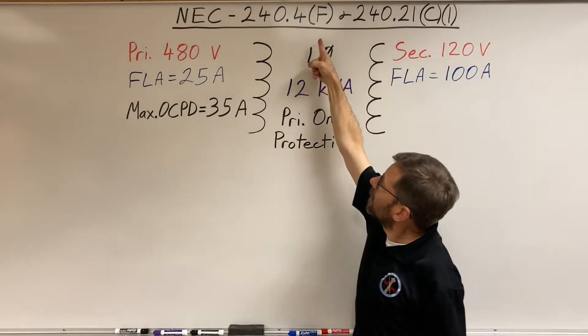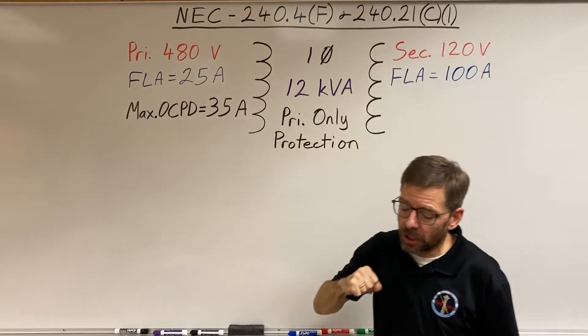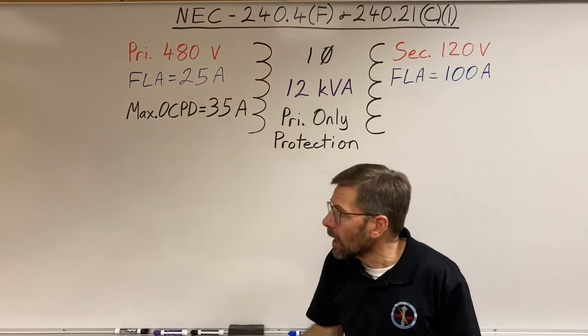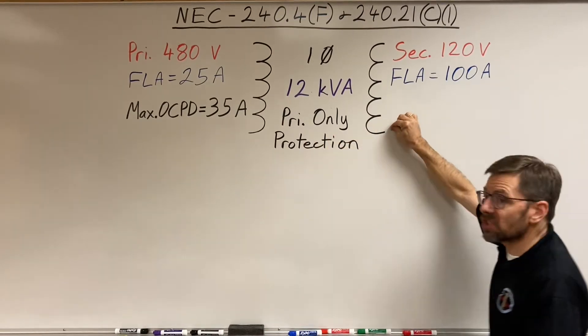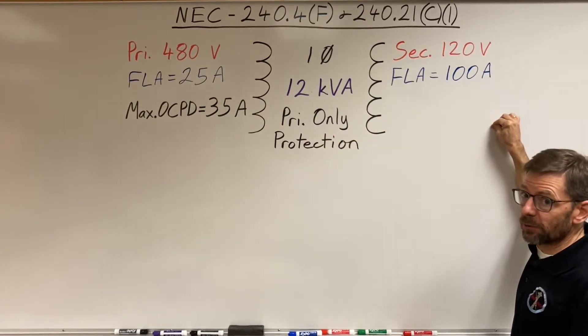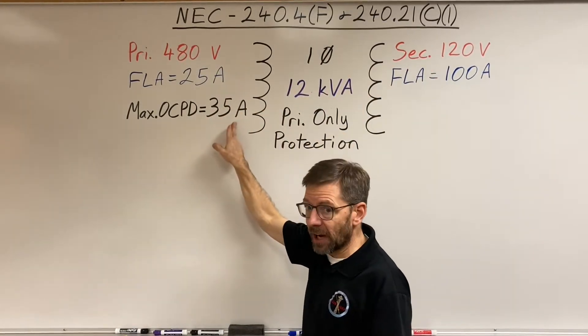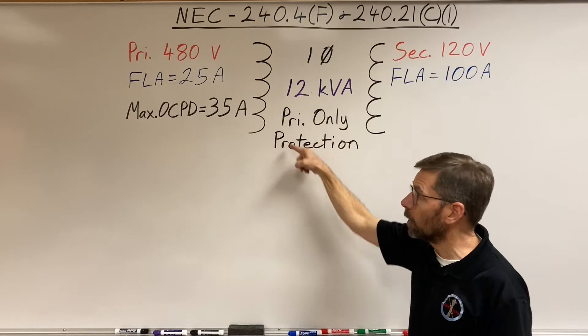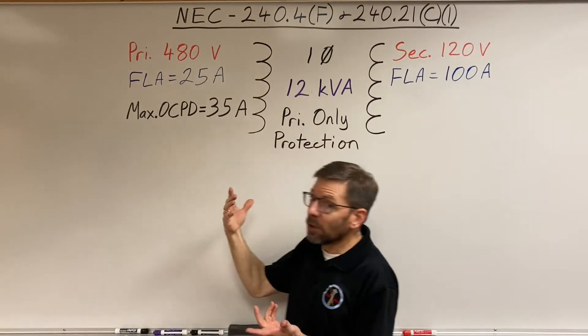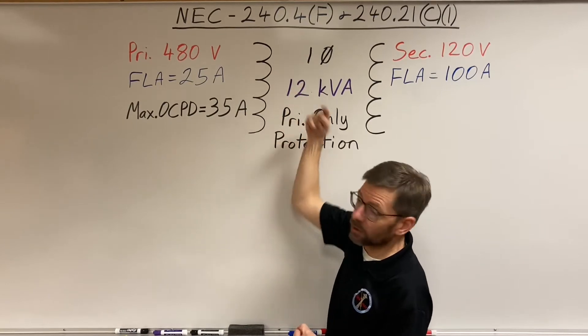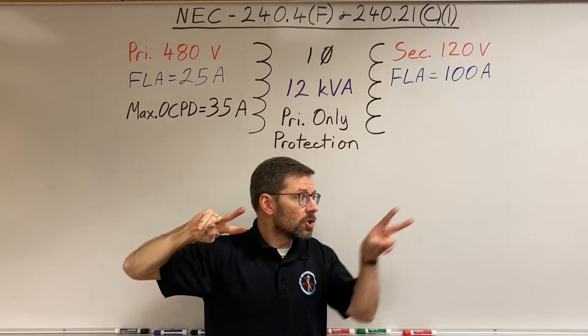So in F and C1, they do the same thing pretty much. What it really tells me is that the only time I can protect a secondary conductor of a transformer with the primary overcurrent device, that means using primary only protection, is when I have a single phase transformer, but it's got to be limited to two wires in and two wires out.